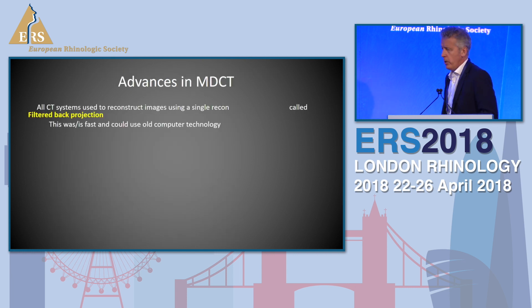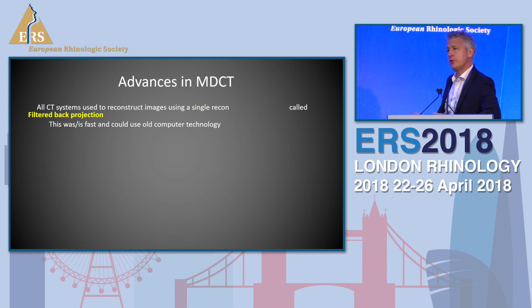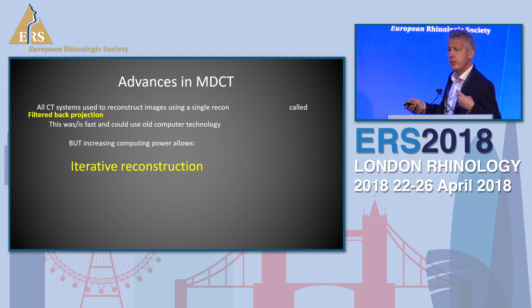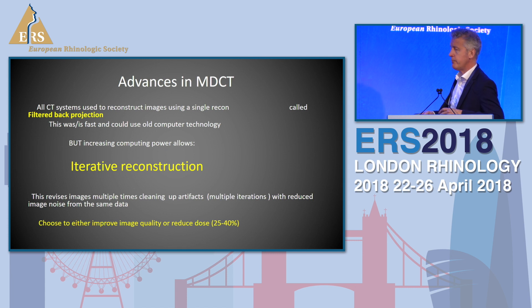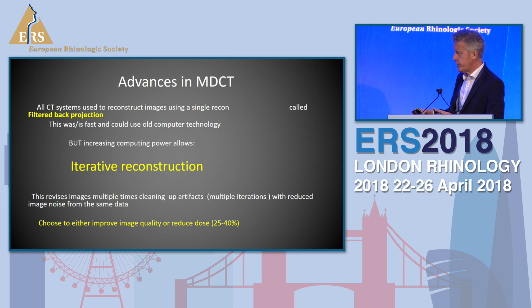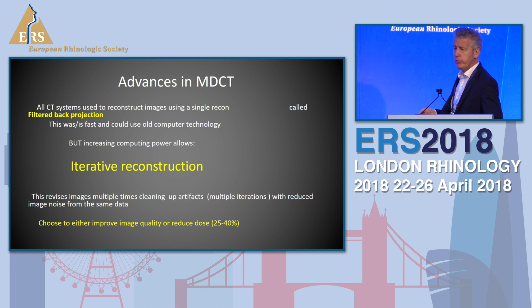What about advances in multi-detector CT? Well, all CT machines used to reconstruct just once and they called it filtered back projection - this is fast and can use older CT. But now we use what's called iterative reconstruction. Basically it means that each image is reviewed multiple times to remove a lot of the noise, and therefore you reduce the image noise from the same data. So you can use that either to improve image quality or reduce the dose.